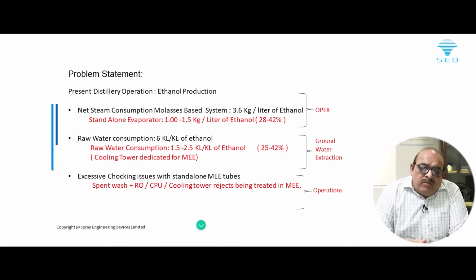When we talk about excessive choking issues, the major issue is that we are using spent wash and mixing it with RO and CPU cooling tower rejects, along with fermenter washing, and using that for concentration in the multiple effect evaporator. When we use this, we experience lots of excessive choking issues.